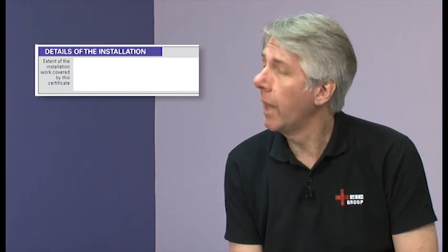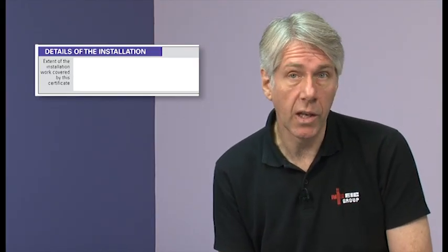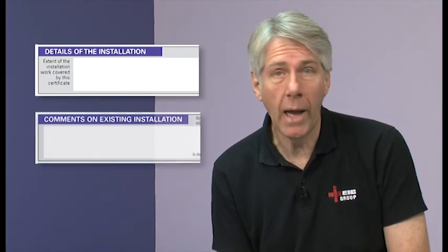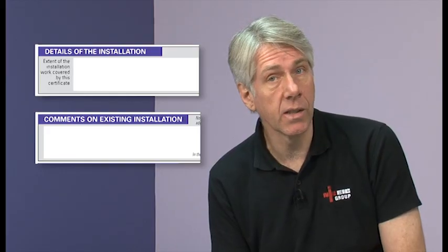This is why both certificates have boxes requiring a detailed description of the installation work covered by the certificate, and also a box to write comments on the existing installation. Presumably, this is a place to record any defects the electrician may have discovered with the existing installation. Yes, but only defects which do not affect the safety of the new work. Now, of course, you've got to use your nous here.